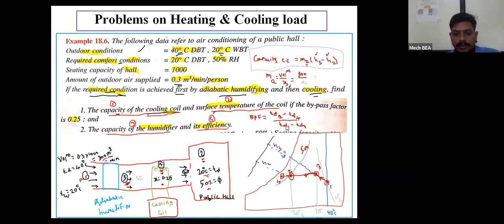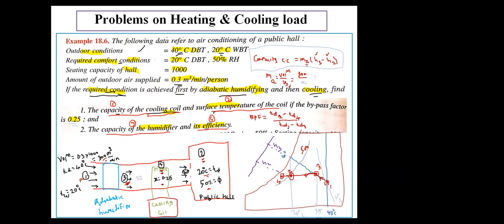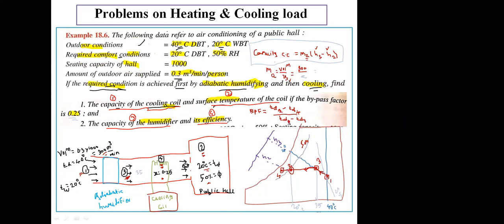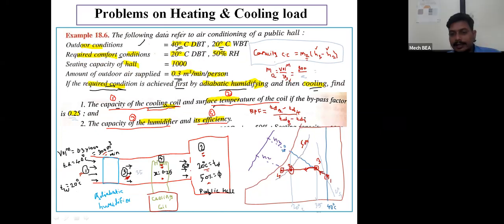So what will be the formula here? For coil and inlet, points 4 and 3 - which temperature is higher between the two? Point 3's temperature is higher compared to point number 4. So here it will be TD3 minus TD4. Until and unless you get the basic concept, you will not get the correct answer. Okay, now you know the bypass factor value.